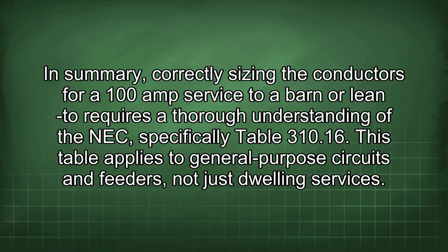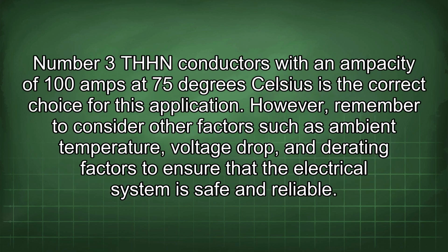In summary, correctly sizing the conductors for a 100 amp service to a barn or lean-to requires a thorough understanding of the NEC, specifically Table 310.16. This table applies to general-purpose circuits and feeders, not just dwelling services. Number 3 THHN conductors with an ampacity of 100 amps at 75 degrees Celsius is the correct choice for this application. However, remember to consider other factors such as ambient temperature, voltage drop, and derating factors to ensure that the electrical system is safe and reliable.